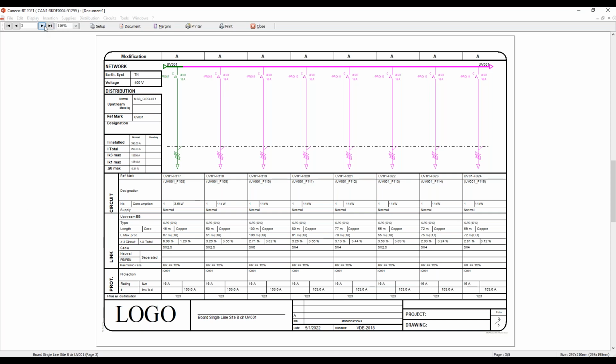Completely forward. So you see, also just go further to the last one, the luminaries, with all the information, with also the power used of L1, L3, or L2, and also here we have full documentation of the cable length, maximum protected cable length, and the factor which is decided that maximum 120 meter could be done is in this indirect contact.